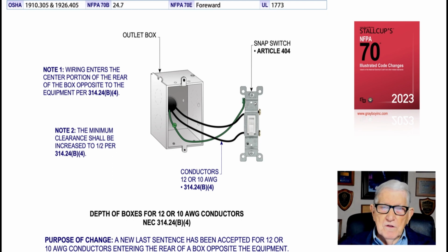Now this illustration deals with the depth of boxes for 12 or 10 AWG conductors in accordance with NEC 314.24(B)(4). Now notice we have these conductors entering the rear of the box. So you need the room to mount that switch to the box and secure it with your screws, and still have room there so you don't mash the insulation, pinch it, or damage it in some way that creates a ground fault or a short circuit. So note 1 kind of explains what the rule is all about.